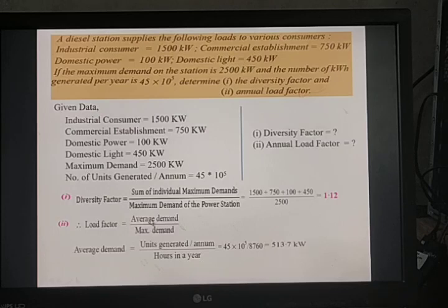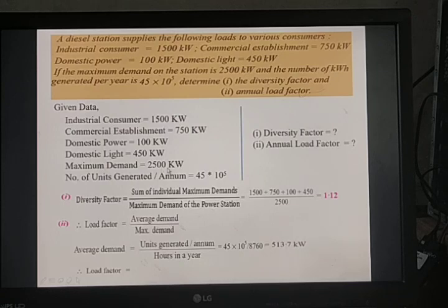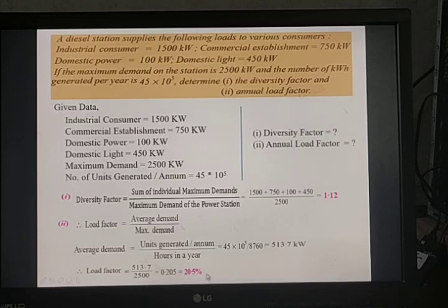Now we can find the load factor: 513.7 / 2,500 = 0.205, or 20.5%. Therefore, the diversity factor is 1.12 and the annual load factor is 20.5%.